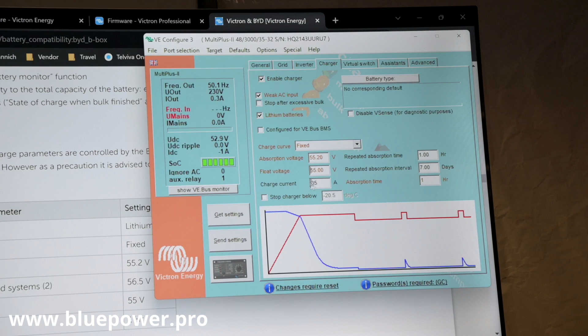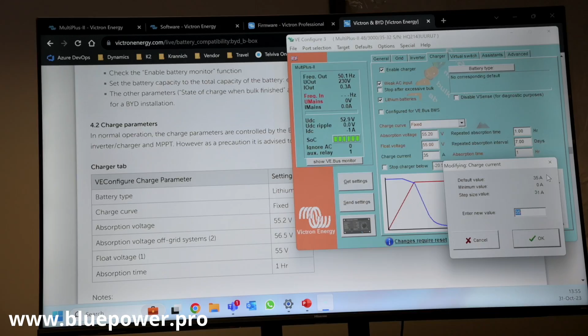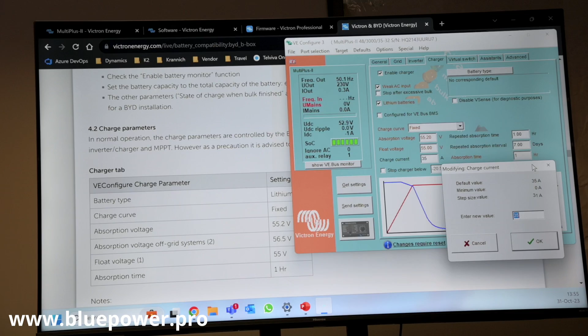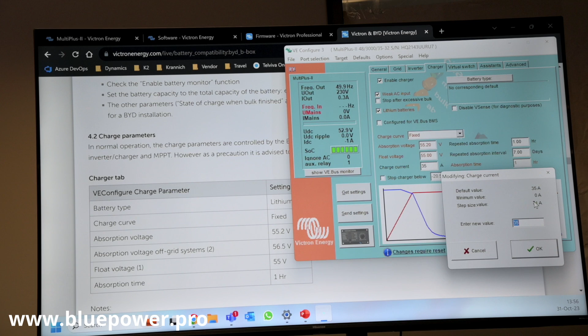Here at the bottom we've got our charging current, so we can open that up. We can see our default value, which is always set at the maximum, so that's DC charging amps. If it's a 48 volt unit, it's going to be 48 volt or 55 volt, whatever your charging voltage is, at 35 amps. Or for the bigger units, whatever their charging amp rating is. If you open it up, you'll be able to see the default value, which is going to be the maximum, the minimum value, and then the step sizes are a bit bonked. For now, they're 1 amp, so you can increment it by 1 amp steps.